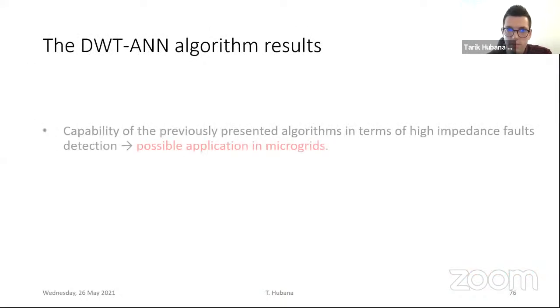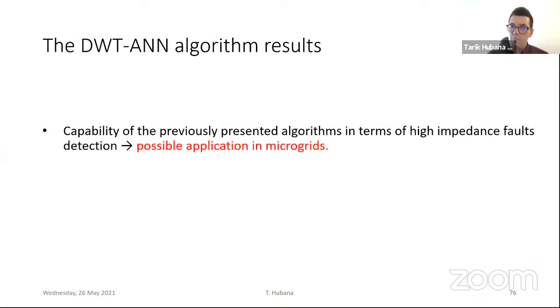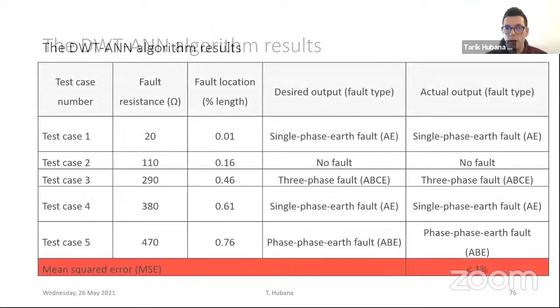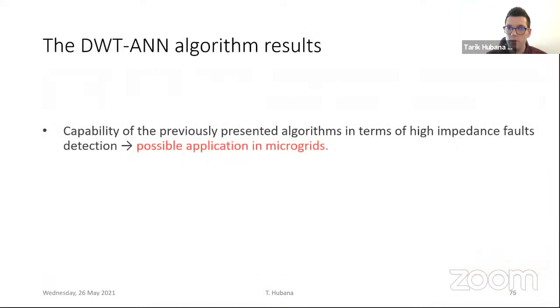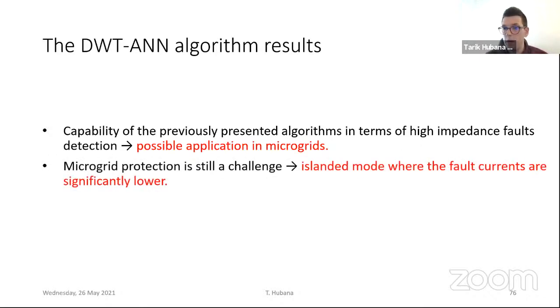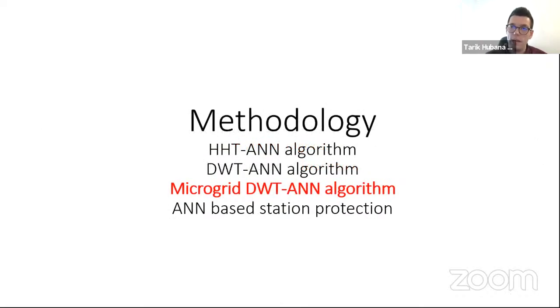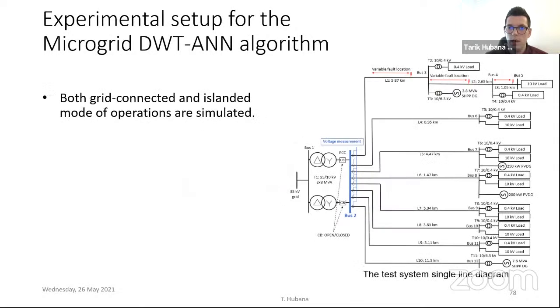So, motivated by the capability of these previously presented algorithms in terms of high impedance fault detection, because we saw that the faults can have a couple of hundred ohms in the fault resistance, which is actually the scenario that occurs in the microgrid when the microgrid works in the islanded mode of operation. Because it is not connected to the primary grid, the short circuit levels are low and the fault resistances are quite high. So the microgrid protection, as we previously presented, is still a challenge, and these 2 research efforts led to an assumption that these methodologies could be used in the islanded mode where the fault currents are significantly lower. So the next algorithm will be a microgrid DWT-ANN algorithm.